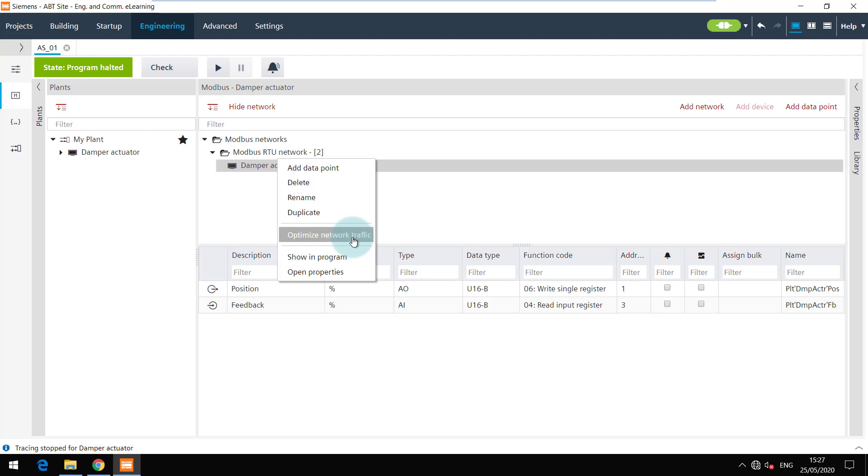The bulk reader object is an octet string calculated value object which reads the consecutively addressed registers in one go. Bulk reader objects reduce the number of requests on the network and thus reduce the network load.